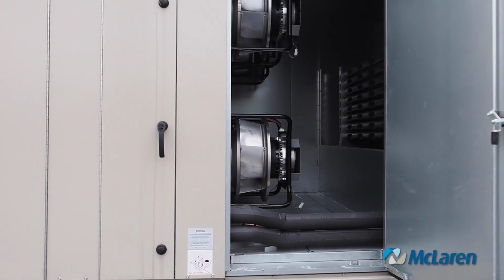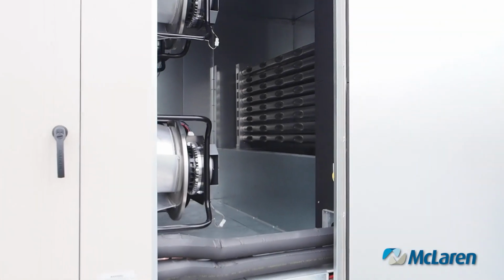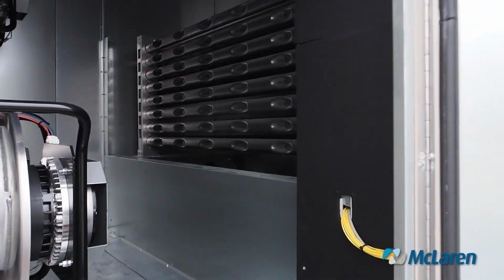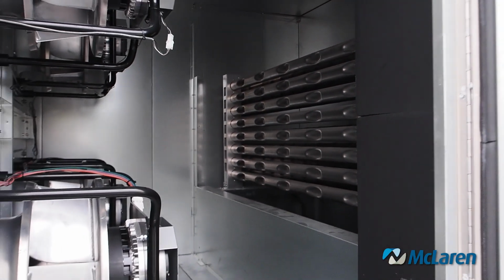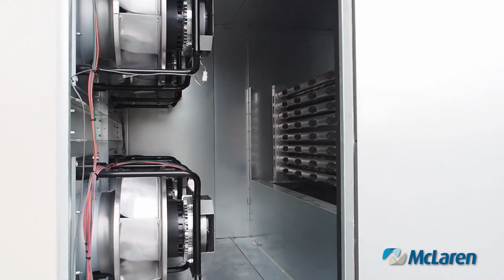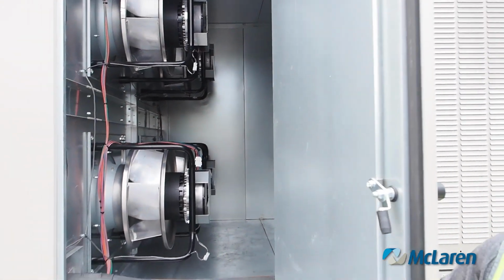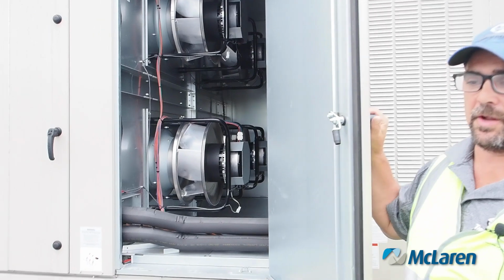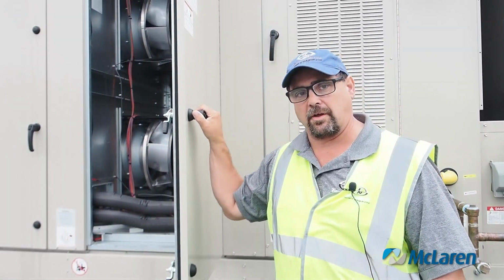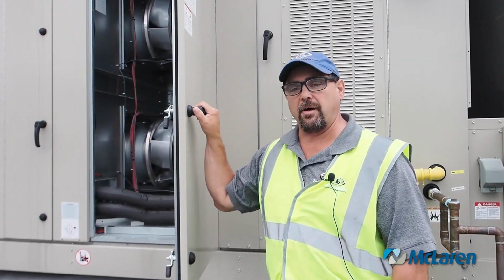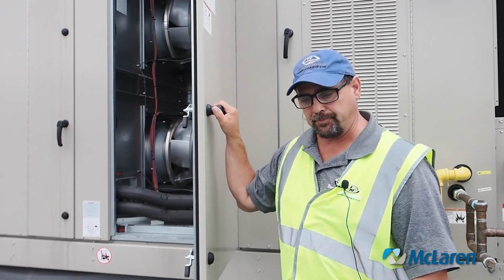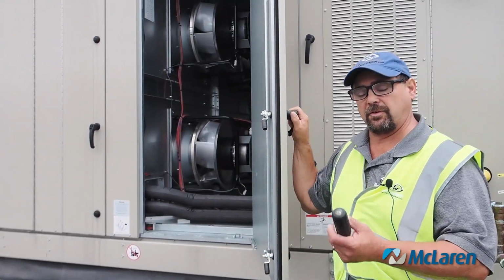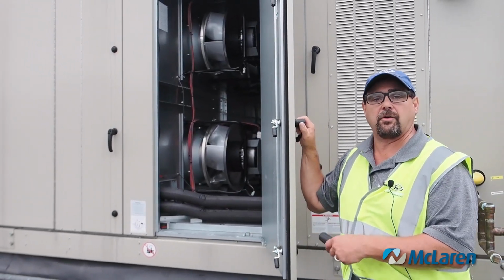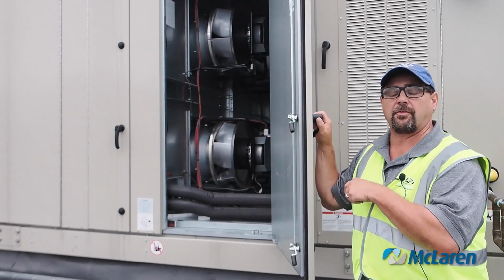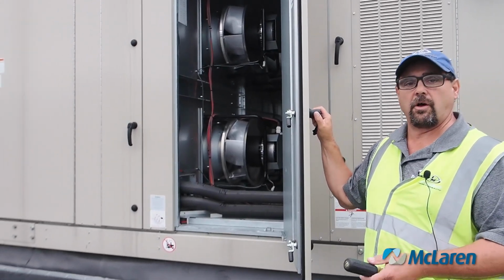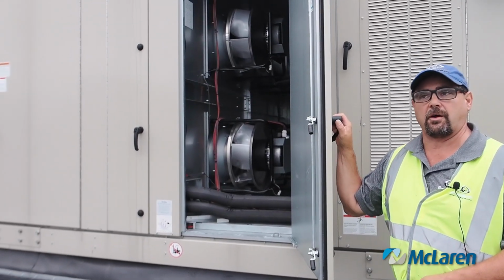This is our supply fan section, and you can also see the heat exchanger from this angle as well. Inside of there are ECM, or electronically commutated motors. They all move at the same speed. So if they're getting a 10 volt signal, they're all going to go at 10 volts or high speed, 5 volts, etc. They all run at the same speed. The beauty part of these, though, compared to the old designs, is that if you lose a fan or one of them fails, you still got 3 others to keep up. In the old world, if you lost a supply fan, you're dead in the water till you got it replaced.